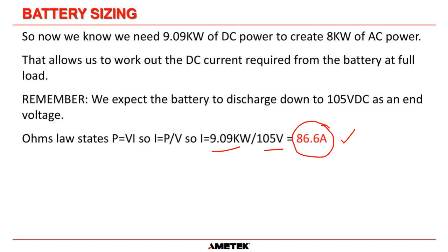So the next question we have to ask ourselves is, how long do we need it to operate? That is decided by the load circuits and the safety requirements at the design stage. If it's a DCS, a distributed control system, most plants want that system to run for about 3 hours. So in this example, we're going to assume the team calculated that we need 3 hours of runtime.